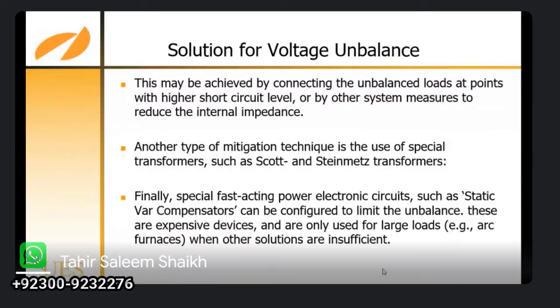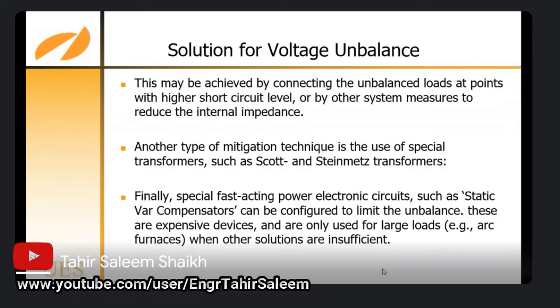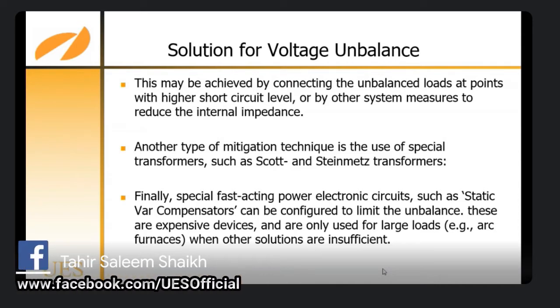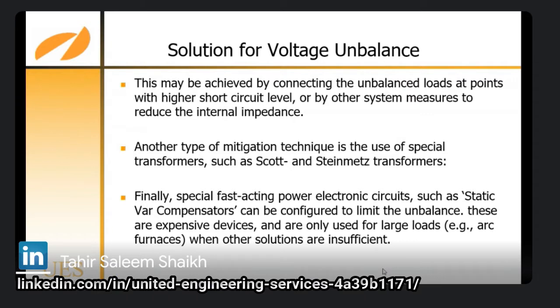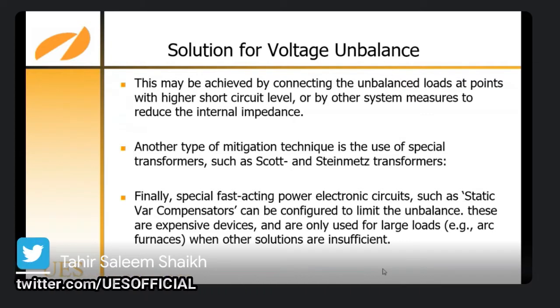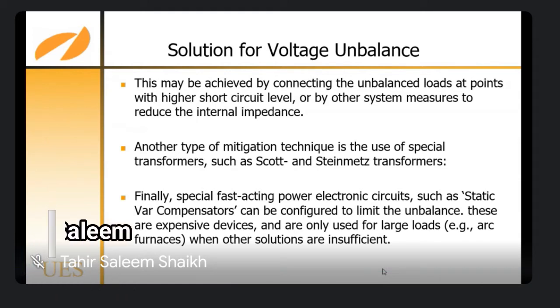Another type of mitigation technique is the use of special transformers such as Scott and Steinmetz transformers. Finally, special fast-acting power electronic circuits such as a static var compensator can be configured to limit the unbalance. These are expensive devices and are only used for large loads, for example arc furnaces, when other solutions are not sufficient. Normally, this var compensator is used on transmission lines.